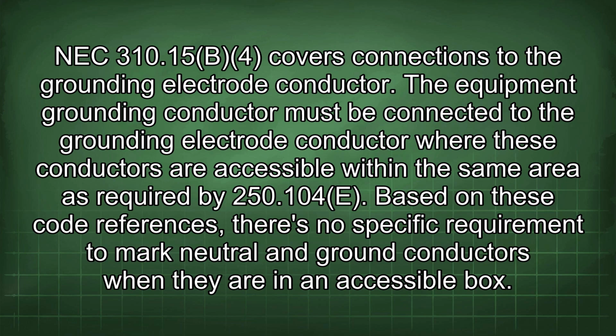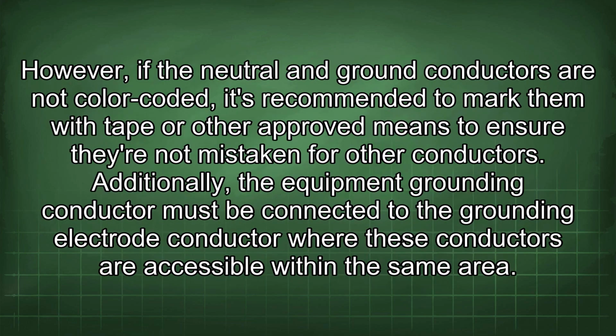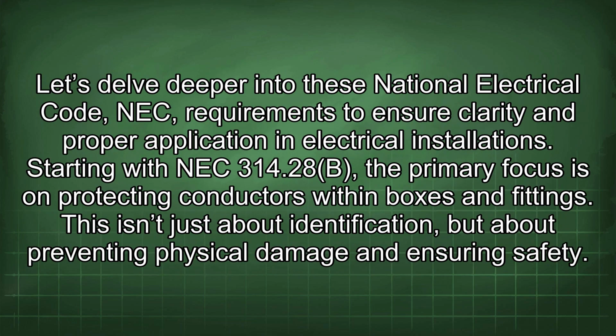Based on these code references, there's no specific requirement to mark neutral and ground conductors when they are in an accessible box. However, if the neutral and ground conductors are not color-coded, it's recommended to mark them with tape or other approved means to ensure they are not mistaken for other conductors. Additionally, the equipment grounding conductor must be connected to the grounding electrode conductor where these conductors are accessible within the same area. Let's delve deeper into these National Electrical Code (NEC) requirements to ensure clarity and proper application in electrical installations.